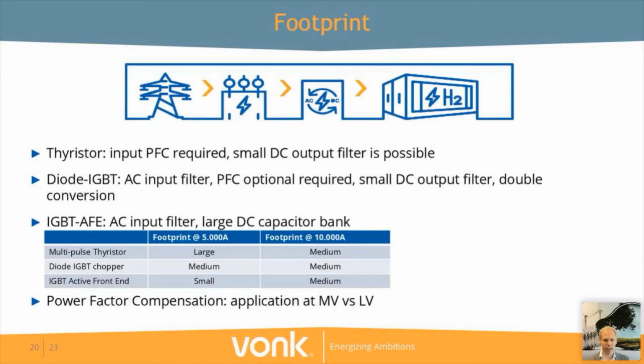And we set up a table to illustrate this a bit, because, for instance, looking at 5,000 amps of current, what you see is that an IGBT active front end requires only very little additional equipment, so therefore has a very small footprint. In comparison, a multi-pulse thyristor solution requires a bit more additional equipment and has a bigger footprint.